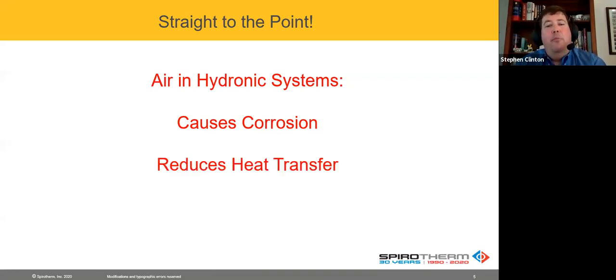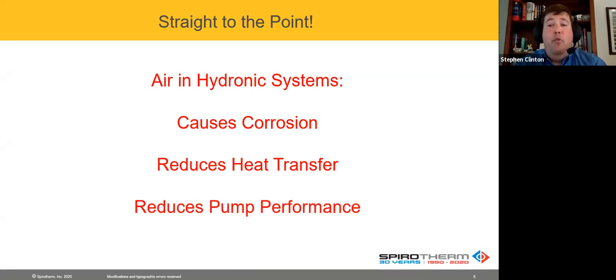More importantly, oftentimes from an energy perspective, and one of the most significant aspects is it reduces heat transfer. We're going to get into why that is, but we need to think about that because that is probably the most important thing. If you don't walk out of this discussion today with anything else, walk out with that. It's really important to know. The other thing is it reduces pump performance. We'll share some industry data that comes from 3 different pump industries or resources that aren't Spirotherm's to tell you how just a very small amount of air in a system can dramatically increase pump energy and reduce its performance.